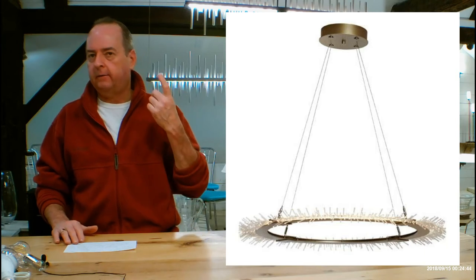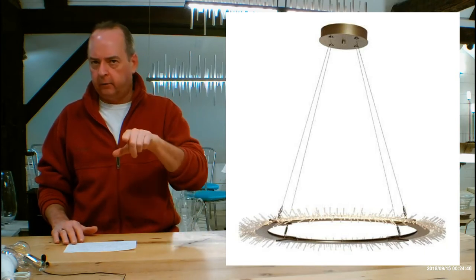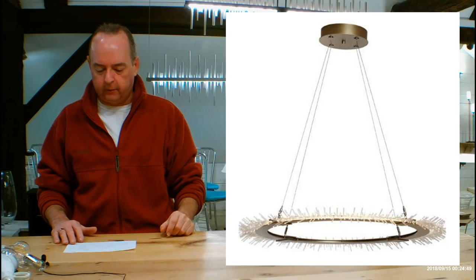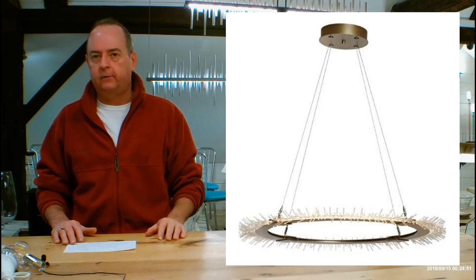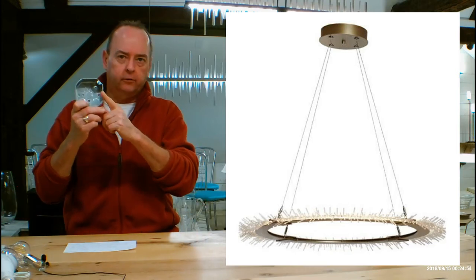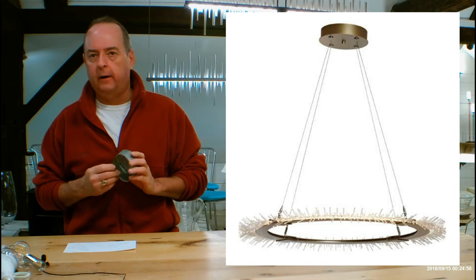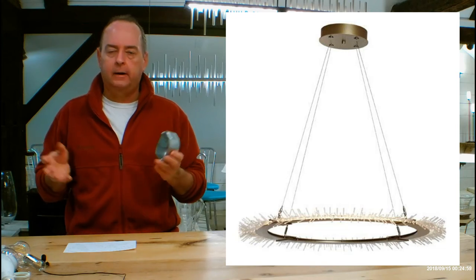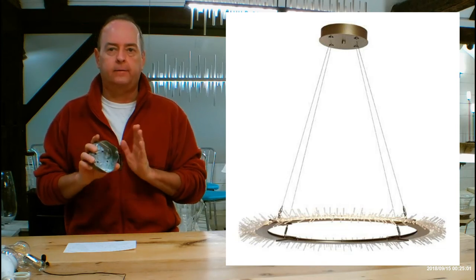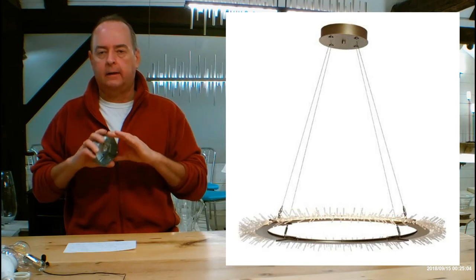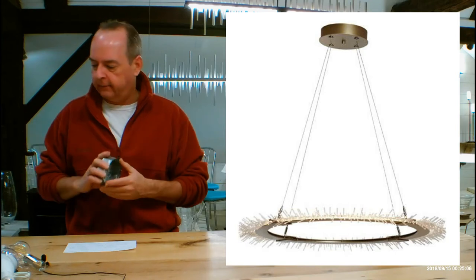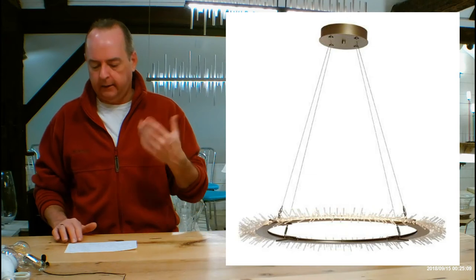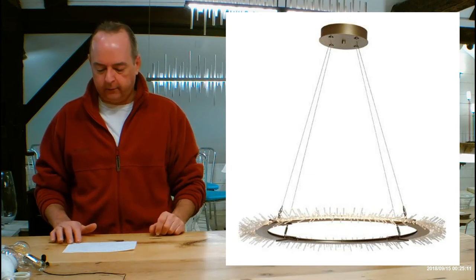Canopy up on the ceiling is 8.5 inches in diameter. That's going to hang from a normal junction box. This is coming in weight-wise at 27 pounds. Anything over 25 pounds, we have to recommend it's hanging from a fan box or some kind of structure, independent of an electrical outlet box just hanging in the ceiling. So talk to your installer that this is going to be 27 pounds.